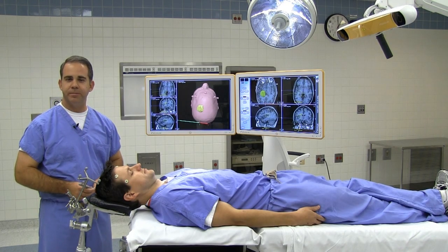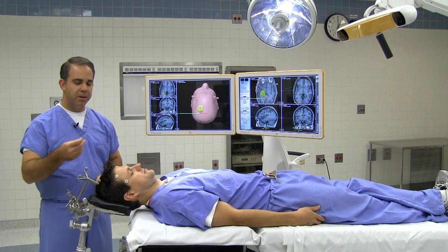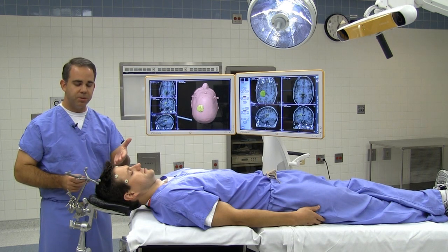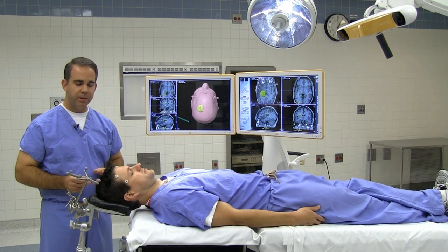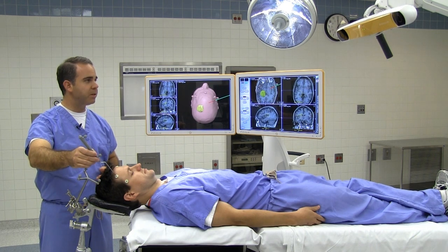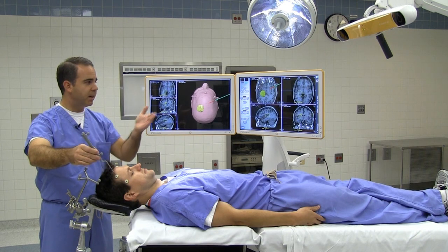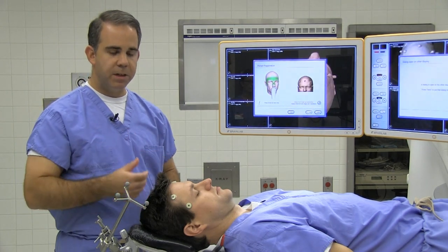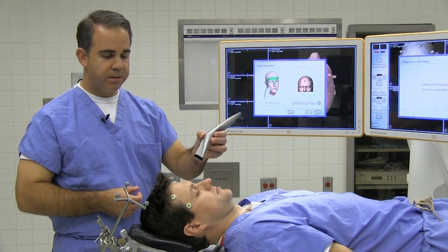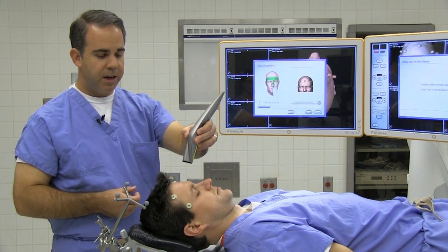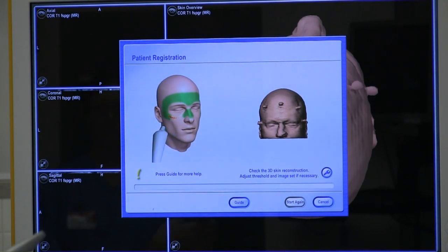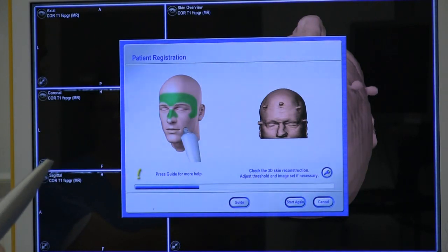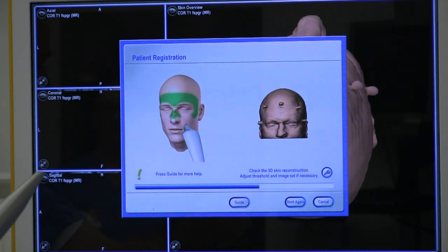The next step is registration — where we're going to bring the patient to match the 3D data from the MRI. The first step is to register the fiducials, the markers that were placed at the MRI, by pointing to them with our pointer. The camera sees the pointer and the antenna and matches those in the 3D map. Another way to register the patient is by using the surface anatomy of the skin. Using this device, the camera can see the surface anatomy, taking multiple spots filling up on the skin to obtain an accurate registration.